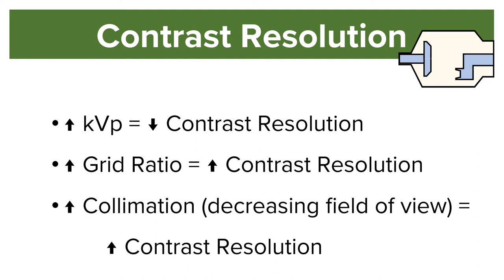Increasing a grid ratio increases contrast resolution because of the decrease in scatter reaching the image receptor. Increasing collimation, or decreasing the field of view, increases contrast resolution because of the decrease in scatter produced.